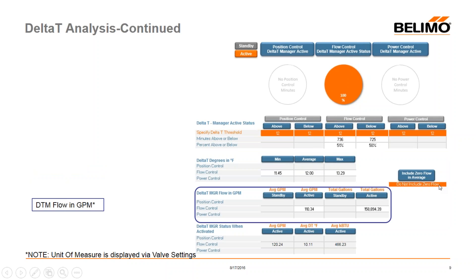Again down below you can include or exclude zero flow, which is important for times when the system is not active. The delta T manager flow in gallons per minute section shows that since the delta T manager was always active in this case, when it was activated we were averaging 110 gallons per minute, and during that active time we flowed this total volume of water.